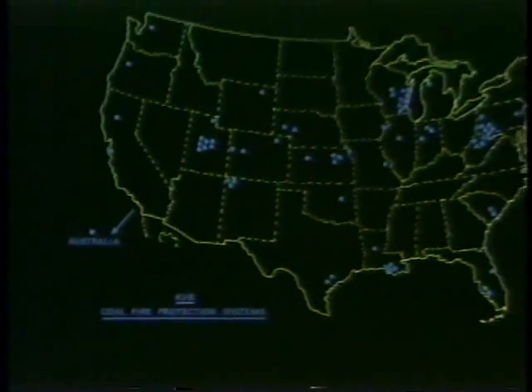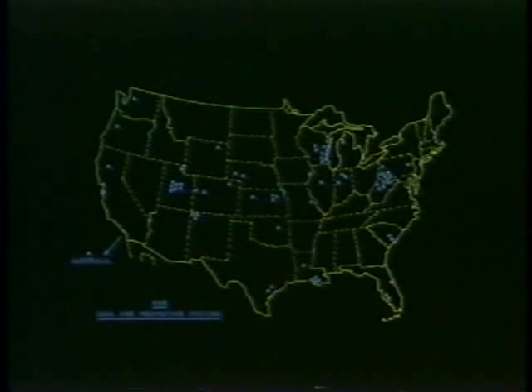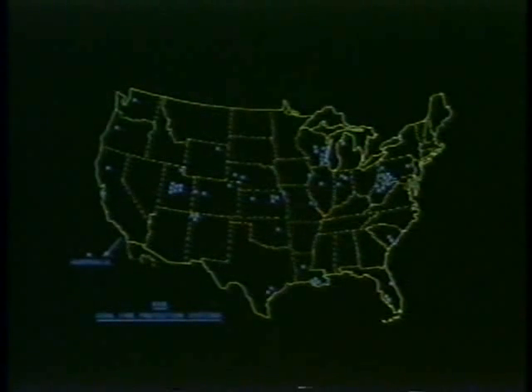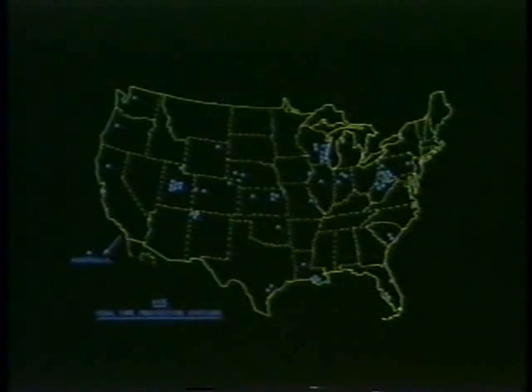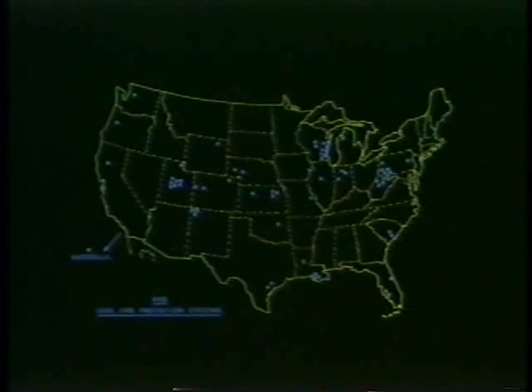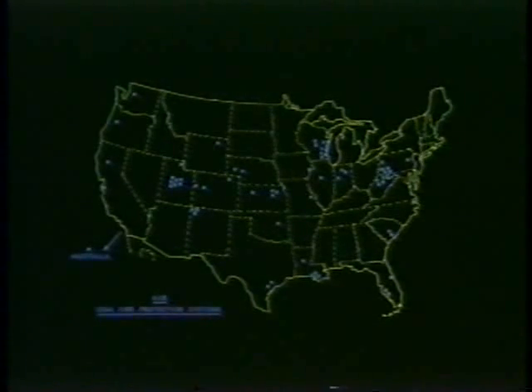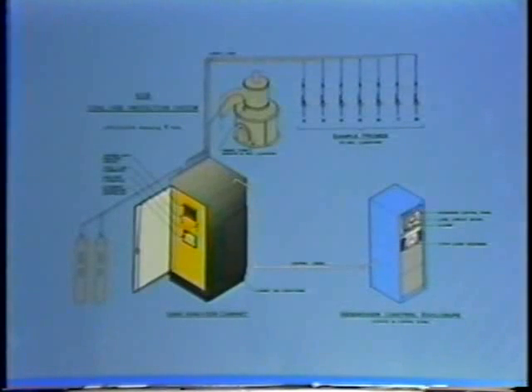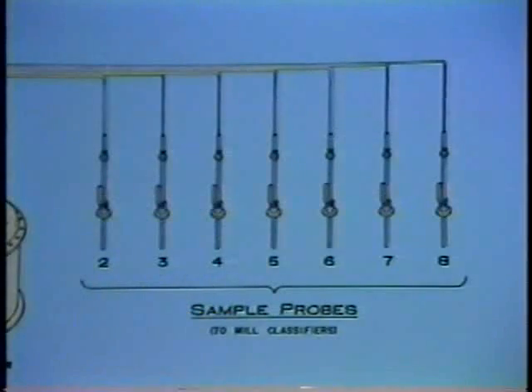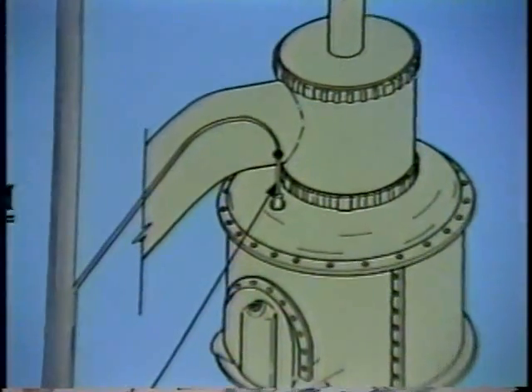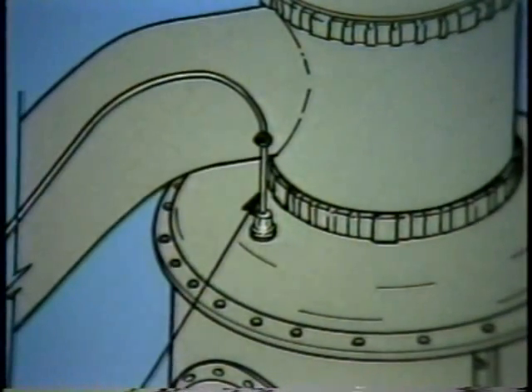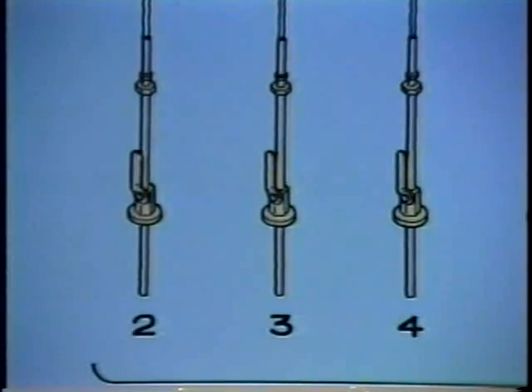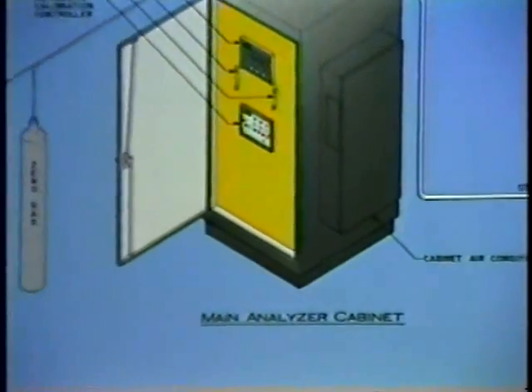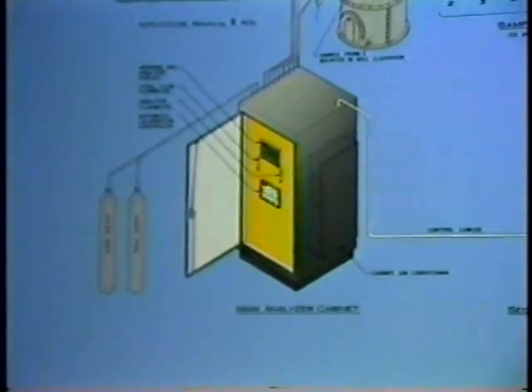Since the successful installation at Public Service Indiana, KVB has installed over 50 additional coal fire protection systems at major utilities throughout the world. The battle against coal fires and explosions is underway. The KVB coal fire protection system is fully automated or can be manually controlled as required. It is designed to monitor up to 12 locations. The system samples the air in the classifier of each mill sequentially through a probe which filters out particulates. The air is dried and sent to an analyzer for measurement of carbon monoxide.